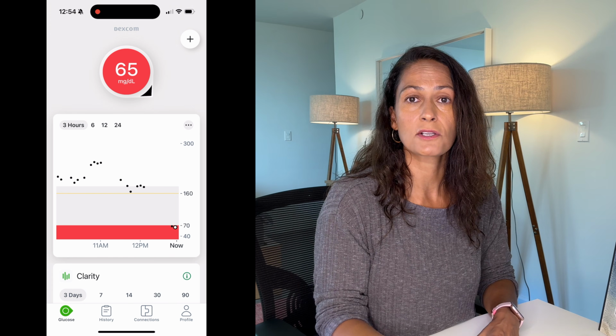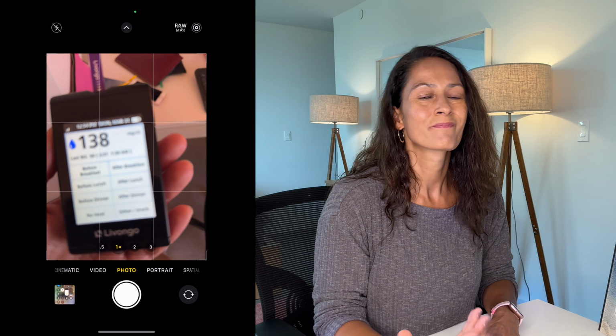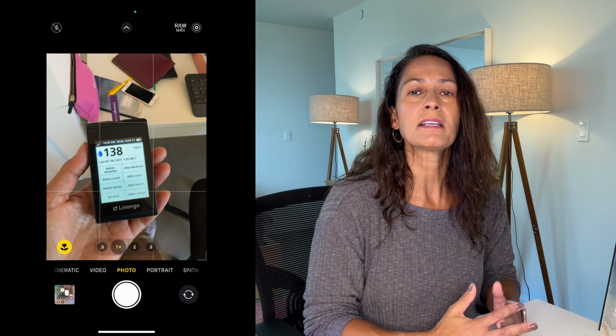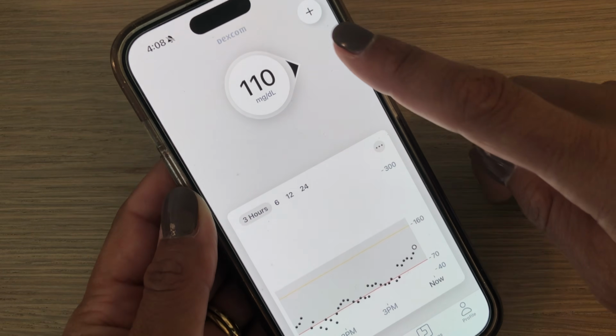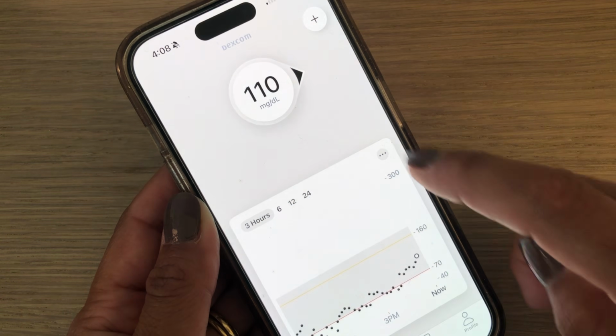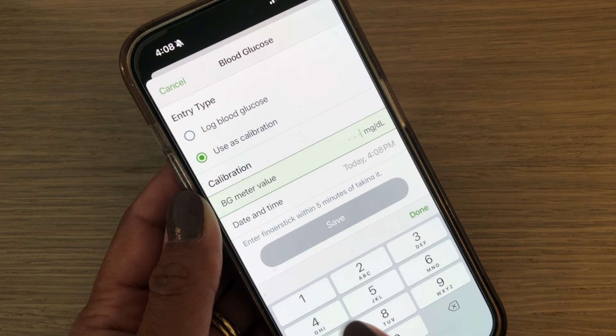And what I found is that Libre starts out strong. It's generally really accurate as soon as it starts, whereas with the Dexcom sensors, a lot of them need at least a few hours before they become accurate. And this is very much in line with my experience wearing the Dexcom G7 sensor. So what I do is that I calibrate the sensor. So that sensor I just showed you, I had to calibrate twice before it became accurate. Calibration means that if, based on finger sticks, the sensor is significantly off, you can add that blood sugar reading and the sensor will adjust.